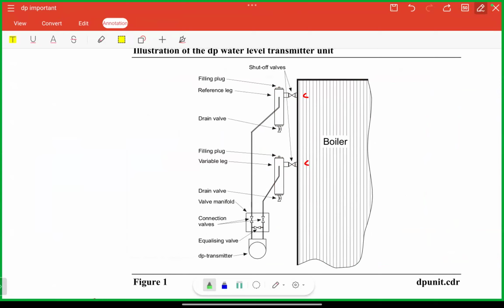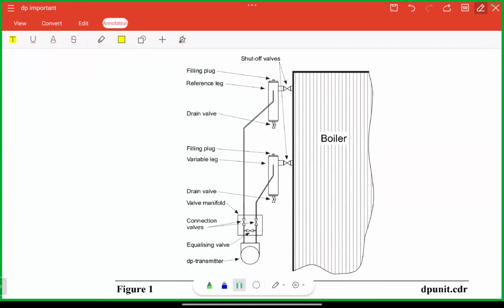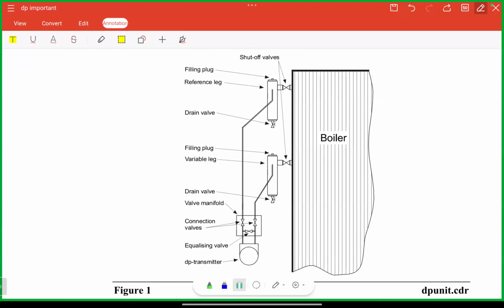And the second point, it will also protect the sensitive equipment or electronic component of your DP transmitter from the effect of high temperature. Third thing, if some sediments, contaminants, or dirt particles are going to come, these are all going to be collected at the bottom of the condensing pot. It will not directly enter the reference leg or your variable leg. Otherwise, these particles and contaminants are going to make their way directly into these small diameter pipes and eventually they are going to choke it. So it is also going to ensure the cleanliness of the system by effectively eliminating any chances of sediment or dirt or dust getting deposited into these legs.